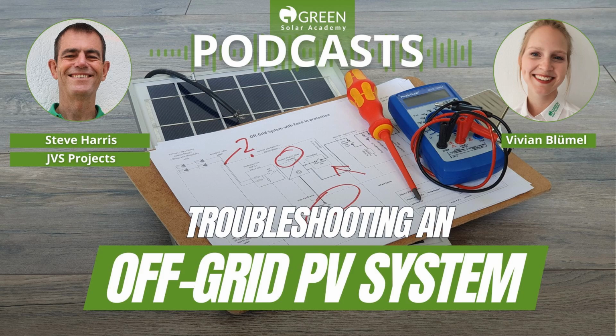Yes, and of course what I didn't talk about earlier on was things as basic as checking your fuse. So when you close the PV fuses again, make sure you've got voltage on the feed side of the fuse and not on the supply side of the fuse. For me, that's just inside there, but it's a basic point. Check your fuse, do a continuity test, and check your cable.